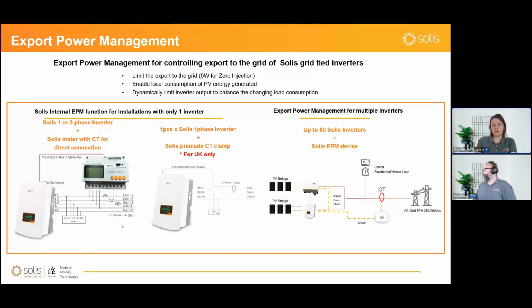So we have two solutions. One is for installations with just one inverter, either single phase or three-phase, and these inverters will be connected to the Solis meter. In some cases, only for the UK market, we have a solution to use a CT clamp instead of a meter, but that's only available in the UK, and it's based on how the inverters for the UK are designed internally as hardware.